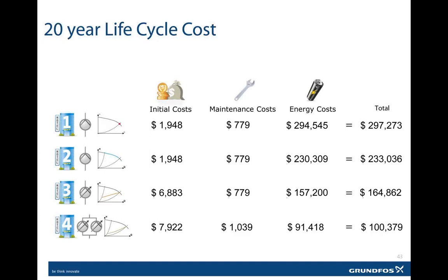Well then if we do the two pumps in parallel, now our initial cost would be $7,922. Our maintenance costs would go up a little bit due to the additional pump required in the system, but now our energy costs have been reduced to $91,418 for a total life cycle cost of $100,379.